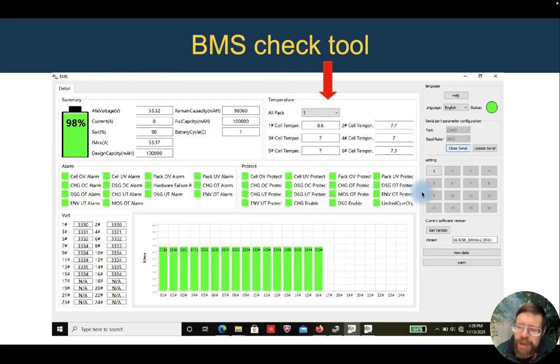On the right side, we've got a couple things which are not used in this software. These are on a different version used for actually programming the BMS, and that's only for the factory to use. I don't even have access to that, because if you program it wrong, you can very quickly damage the battery, definitely void the UL listing, and possibly make it unsafe if you've programmed the wrong parameters into the BMS. That's why the version we release for everyone to use is basically read-only - you can't actually program the BMS, because that introduces way too many potentials for destroying the battery.